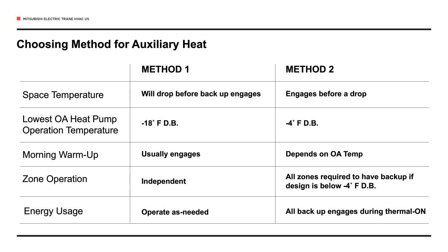Also with method 1, we want to make sure that we don't size our heaters too big. We've seen this on ducted units where we have a downstream electric heating coil, and if that heating coil is sized for too big a delta T, because you're running the heat pump heat and the auxiliary heat in series with each other, you have an additive delta T. So if your heat pump heat is giving you 20 degrees delta T and your electric heaters are designed for 30 degrees delta T, you're going to have a 50-degree delta T coming off that unit, and that could be problematic. So we always advise design engineers to size the heaters in method 1 for the difference between what the VRF unit is doing heating capacity-wise and the space load.